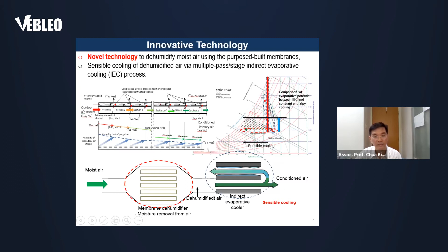But using part of the dry air to vaporize the water in the adjacent channel so that it can cool the dry channel. That means you're using the water layer in the wet channel to cool the dry channel. And in that sense, we actually accomplish what we call the air conditioning effect, using the membrane to remove the moisture and using a dew point evaporative cooling system to do the cooling.